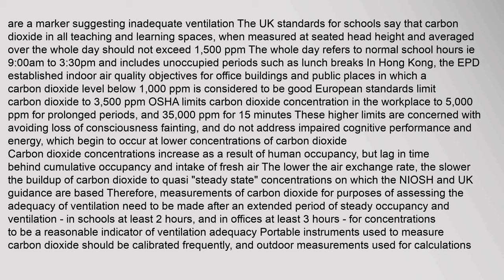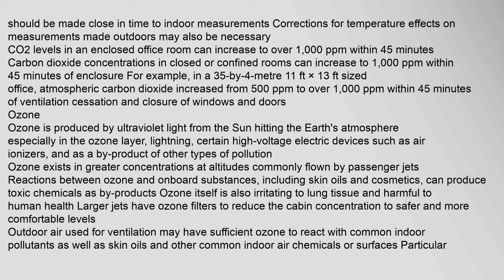In Hong Kong, the EPD established indoor air quality objectives for office buildings and public places, in which a carbon dioxide level below 1000 ppm is considered good. European standards limit carbon dioxide to 3500 ppm. OSHA limits carbon dioxide concentration in the workplace to 5000 ppm for prolonged periods and 35,000 ppm for 15 minutes. These higher limits are concerned with avoiding loss of consciousness and do not address impaired cognitive performance, which begins to occur at lower concentrations.